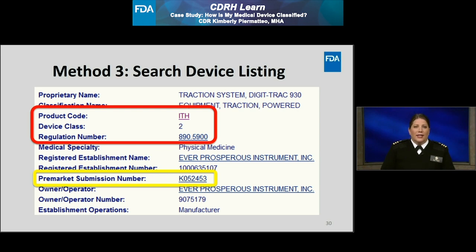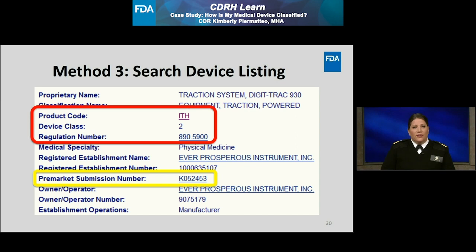Under this device listing, I can review information about how this device has been classified to determine if the same classification applies to my device example. Highlighted in red, I can see the Digitrack 930 falls under the product code ITH. It is class 2 and the applicable regulation is 21 CFR 890.5900. This is the same classification information I was able to find by searching the two previous methods. If I want to review more details about this device type and classification, I could again select the hyperlink to the ITH product code or hyperlink to the regulation number. I could also select the 510K number, highlighted in yellow on this slide, and it will take me to the 510K clearance database where I can review the 510K summary for this device.